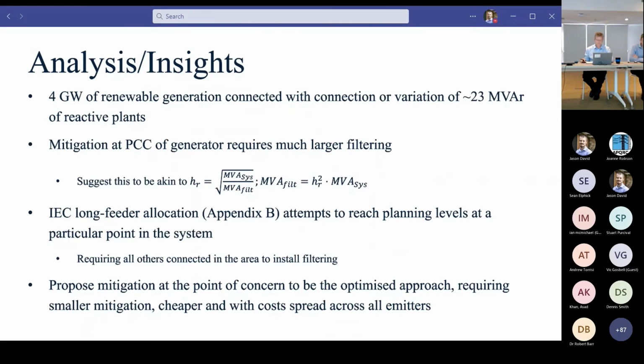What we found, and there's a full discussion in the report itself, is that we just kept connecting large generation to this network, which had quite a lot of weak areas. But we had 4 gigawatts of generation connected with roughly 23 MVAR of reactive filtering required. A number of reasons for this, but ultimately what we can show is that the filtering at the weaker points of the network, the size of the filter needs to be much smaller, because it has a much larger impact on the harmonic impedance of the network itself.